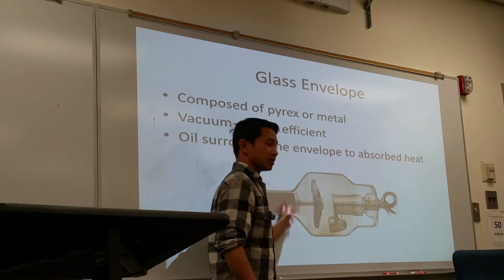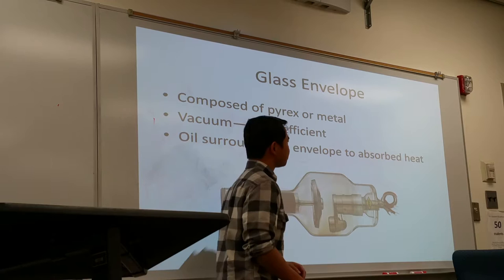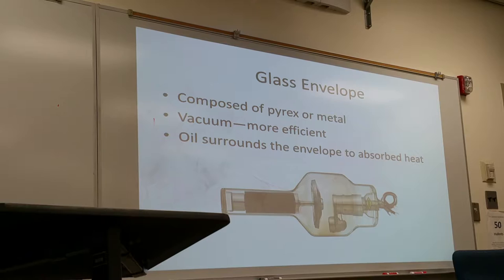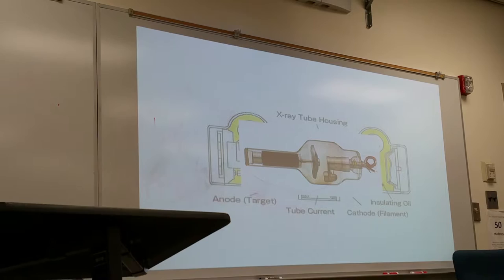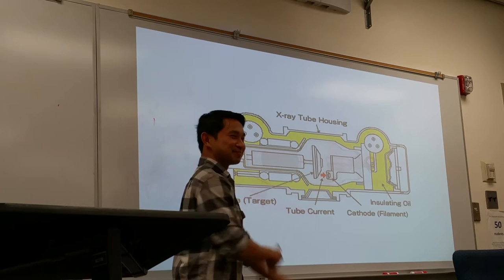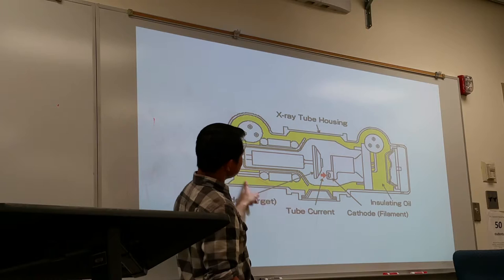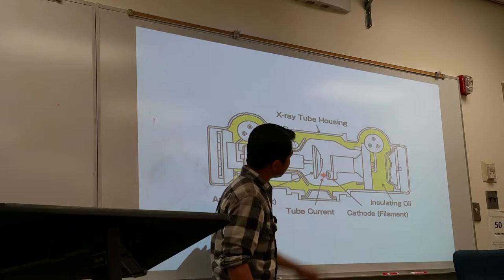Oil surrounds the envelope because it is inside the metal housing, and the metal housing has oil all around it to absorb heat. So the structure is: the envelope inside, surrounded by oil, with electron production occurring inside producing x-rays that come out through the window.